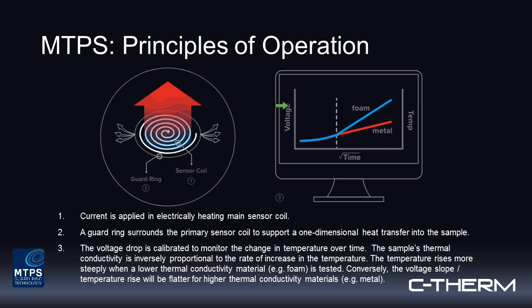Back to what the raw data looks like, you have your voltage time curve, which is calibrated to your delta T over time. And these slopes are inversely proportional to thermal conductivity. So for something like a foam that's very insulative and low in conductivity, you're going to have a much steeper slope than something conductive like a copper or a metal sample.